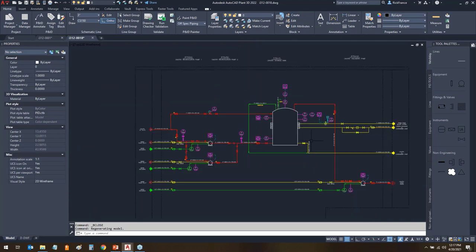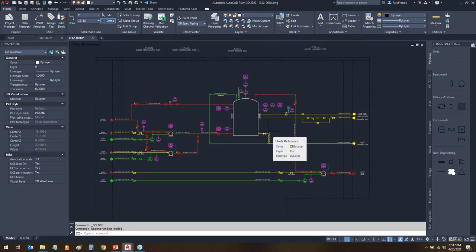Right now, the P&ID, as far as AutoCAD is concerned, is ready to go. I'm ready to move this into P&ID. So I'm going to start with the line work for the project. Well, first I need to show you what you need to be aware of project setup wise. For instance, this line here is going to be that P-3 layer. That's the tertiary line. If the tertiary line doesn't exist in the P&ID project, you won't be able to convert to it. So I've got a tertiary line here that's in my custom line. It's not there out of the box.